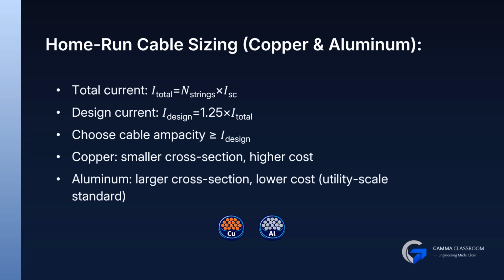To size the home run cable, we start with the total short-circuit current of all strings, multiplied by 1.25 for continuous duty, and then choose a cable whose ampacity meets or exceeds that value. Copper requires a smaller cross section, but is expensive for long runs. Aluminum requires a larger cross section, but dramatically reduces cost, which is why it's standard in utility-scale solar farms.